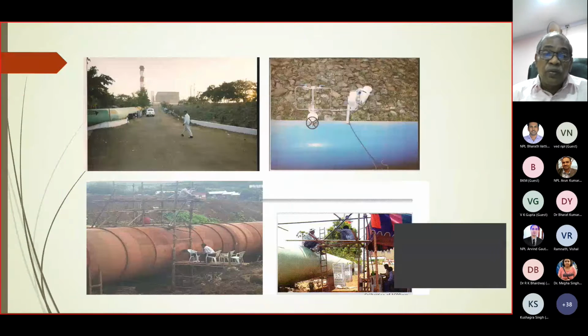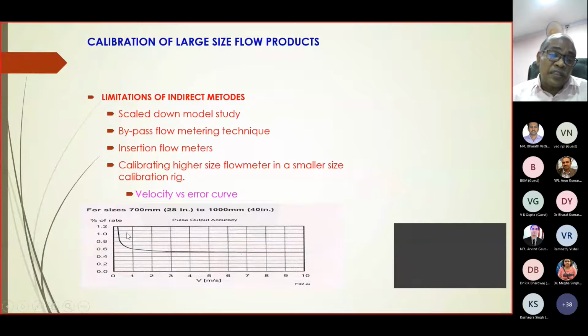See, if you look at the error curve of flow meters, this is for an electromagnetic flow meter, the accuracy or error will be constant after a velocity of 1 meter per second. So below 1 meter per second, the error is not constant.